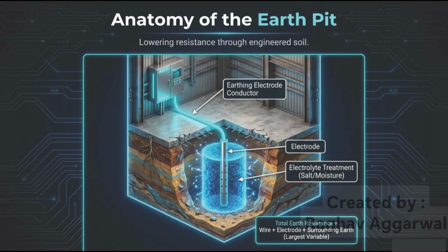The electrode creates the physical connection between the plant and the surrounding earth. The electrolyte treatment, using salt or moisture to improve the conductivity of the surrounding soil, helps to lower overall resistance. Notice the formula shown as well. Total earth resistance is influenced by the conductor, the electrode, and the surrounding earth. The surrounding soil is identified as the largest variable because soil conditions can change due to moisture content, temperature, and composition. An effective earth pit must maintain low resistance so that fault current can flow quickly and safely into the ground.